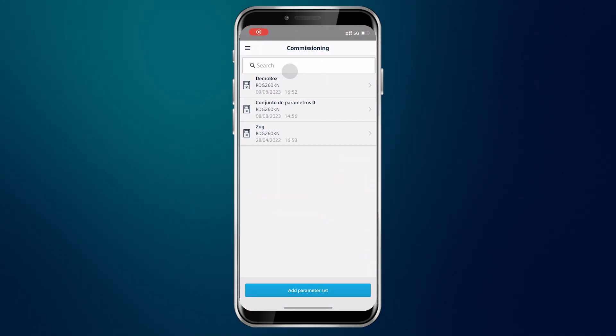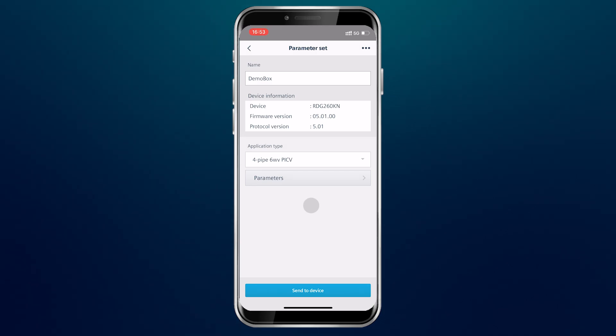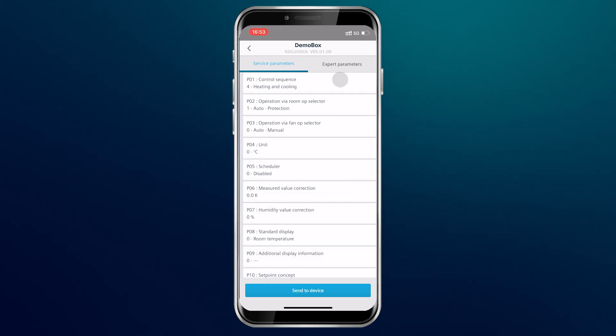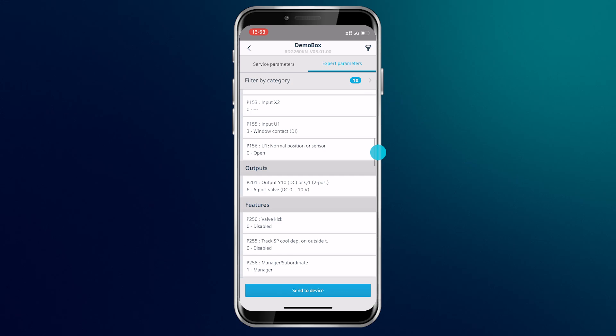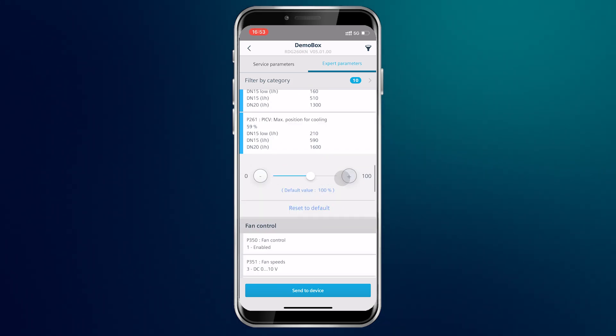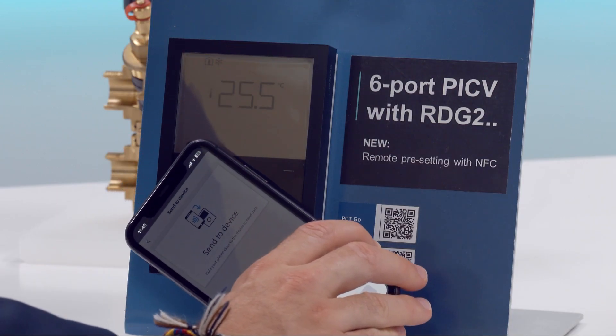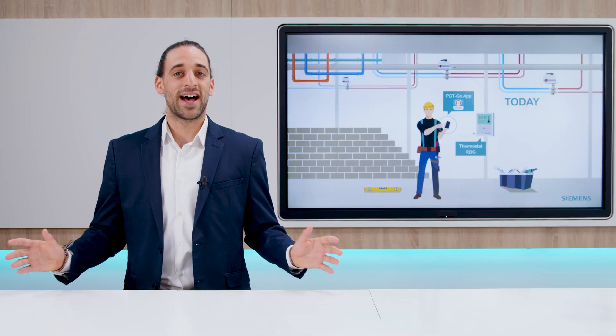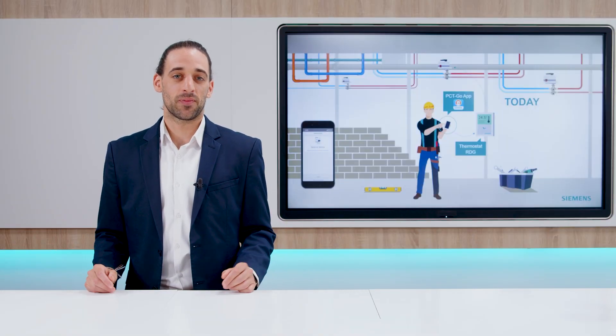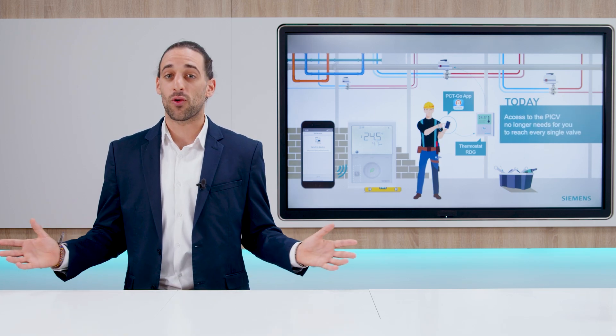Open the PCT Go app in your mobile phone. Select the four-pipe six-port PICV application and set the right flows for heating and cooling. Save it and send the data to the RDG thermostat via NFC. That's incredibly easy. On-site commissioning is now extremely fast for you, with a very intuitive workflow-driven process.